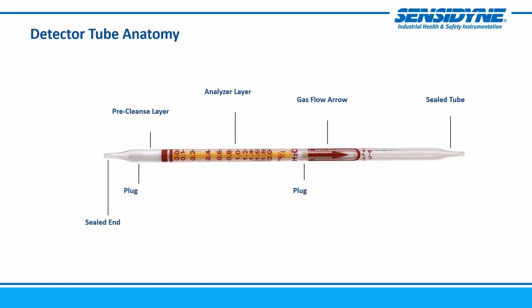The first thing you'll see to the left is what looks like a white, almost cotton or foam plug. This is typically for removing moisture, relative humidity that might be in the air, because it could impact the reagent in that analyzing layer. Another factor is that sometimes it actually contains another chemical reagent, which would be a precursor for the reagent that is in the analyzer material. That information usually is specified within the instruction sheets for that specific tube.